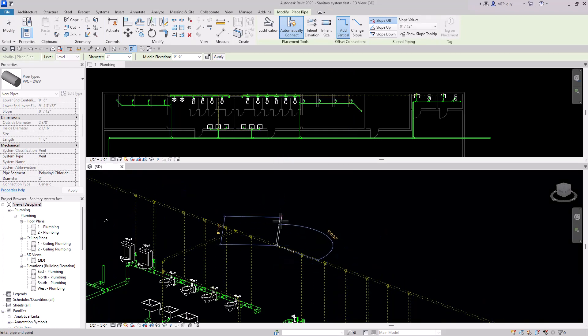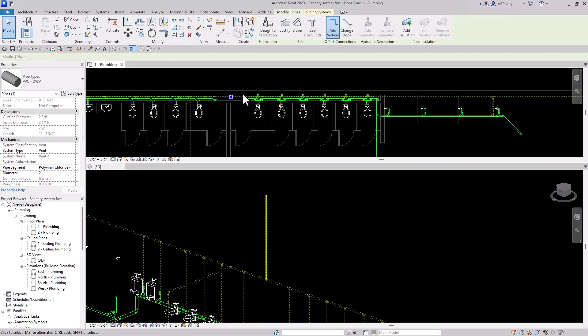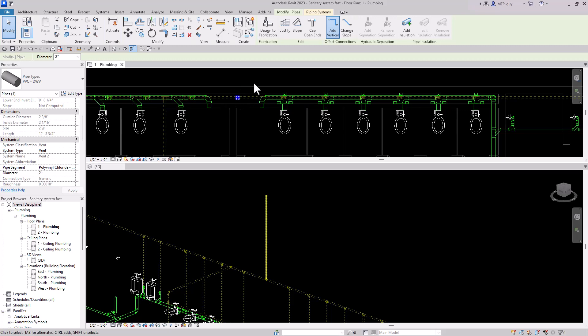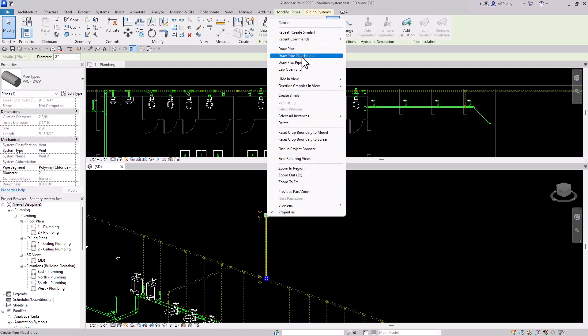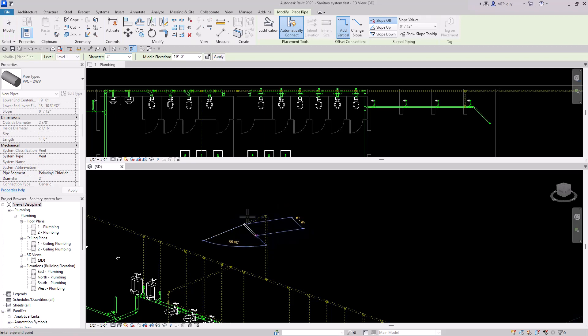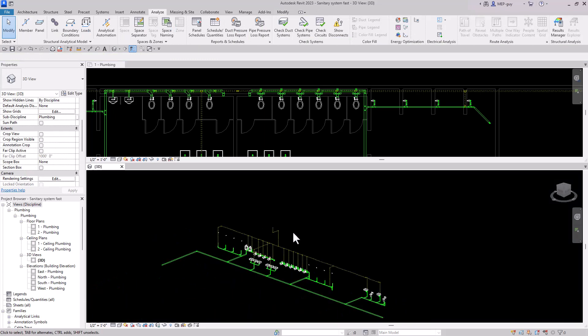We've basically finished the vent system for this building, but we obviously need the vent through the roof so our plumbing system can breathe. I'll pick a spot — click on the pipe itself, create similar, and bring it up to 22 feet since the building is about 20 feet high. Actually, this location is too close to the edge of the building, so for waterproofing purposes we want to bring that vent piping more toward the center. I'll bring it below the ceiling to 19 feet, draw a pipe holding shift in the other direction, then bring it up to 22 feet. Now the piping makes a little offset so it's more centered on the roof.